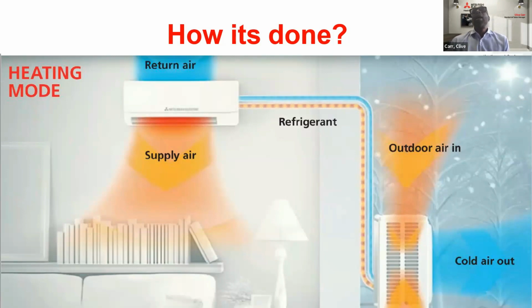Now, one may ask, how could you extract heat from the air when the outside temperature is -15, -20, -30? That's done with the refrigerant. The refrigerant is a liquid that boils at a very low ambient temperature. So you could have the liquid boiling as low as -25, -30. There's still enough heat in the outside air to be absorbed and to boil off the refrigerant. So the cooling cycle is reversed, providing heating in the space. And then in the summer, the cycle is reversed, providing cooling. So in one system, you're able to achieve heating and cooling operation.